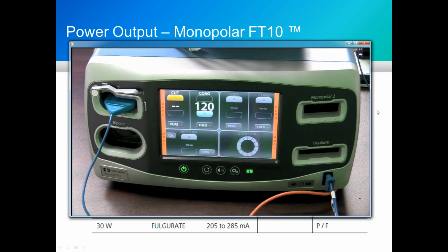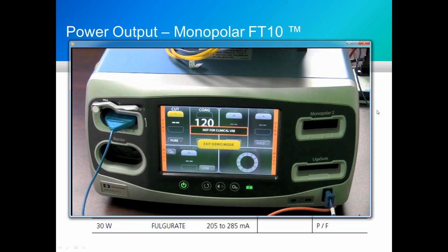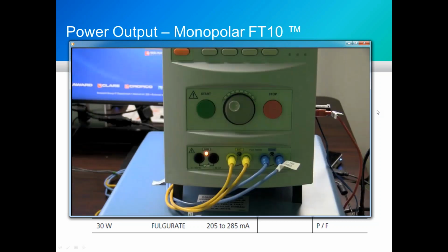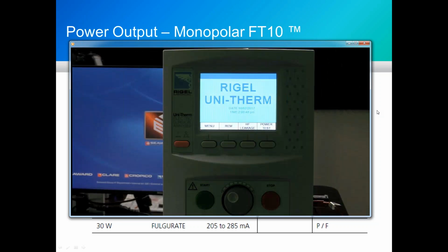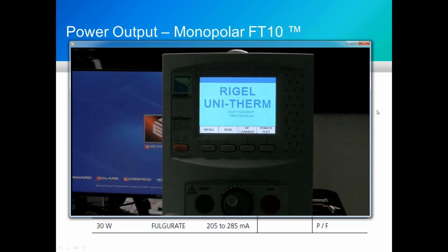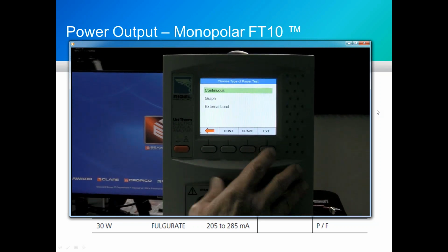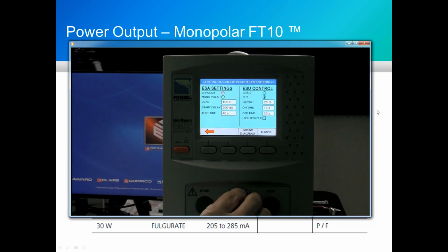Set the power to 120 watts. I have foot switch cables with a contact closure that the Unitherm will provide us that will energize the generator, and that saves us a little bit of time in the PM process. I'm going through now and setting up the screen for the CoAG test, setting my resistance to 500 ohms. Now I'm doing manual testing here. If I was doing this as part of an automated test sequence, which we have for the FT10 along with a number of other generators, all of the information here would be pre-populated for us.